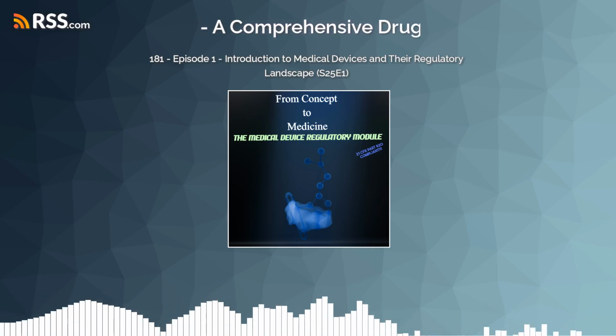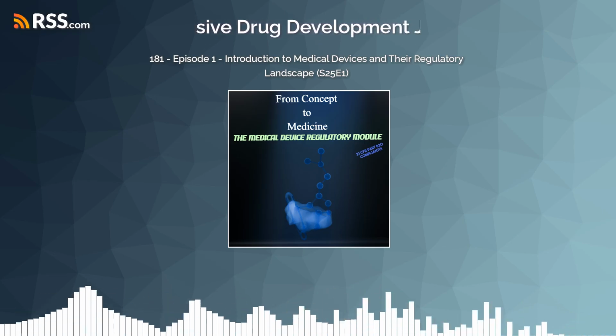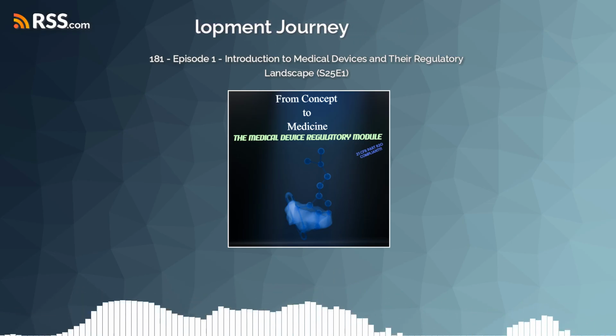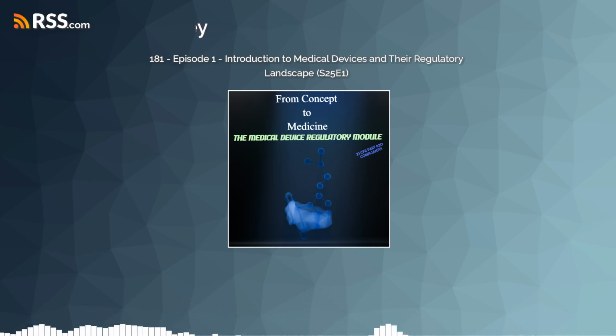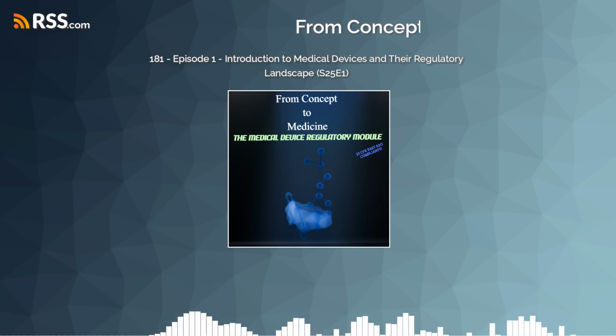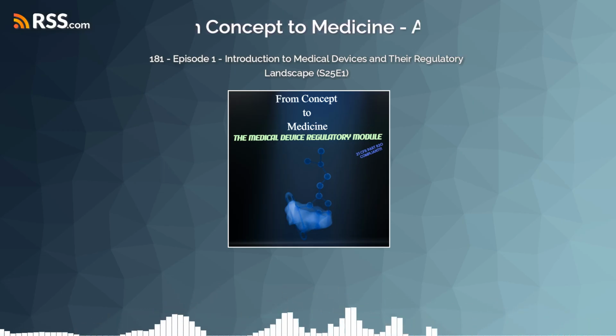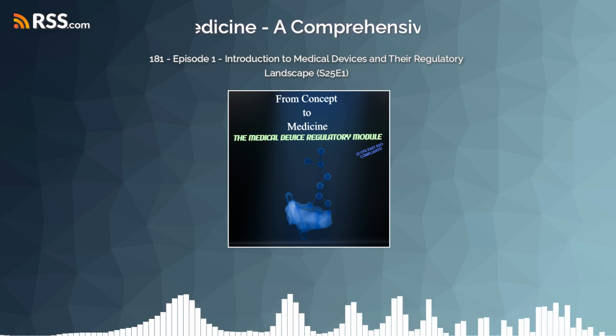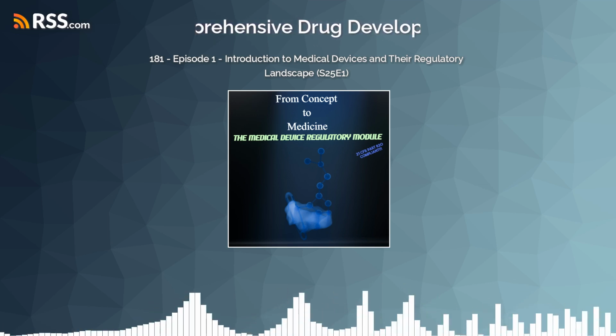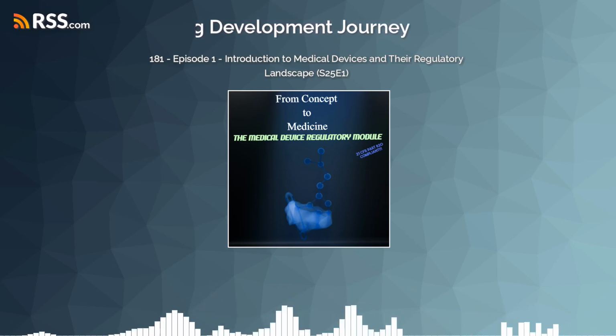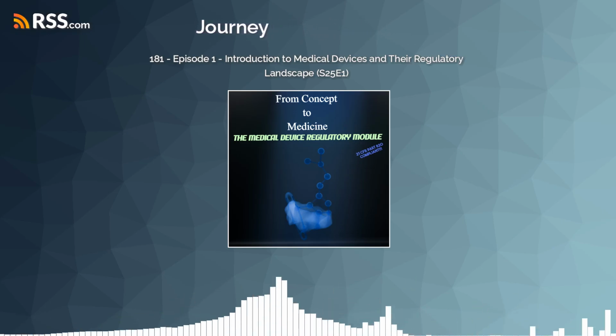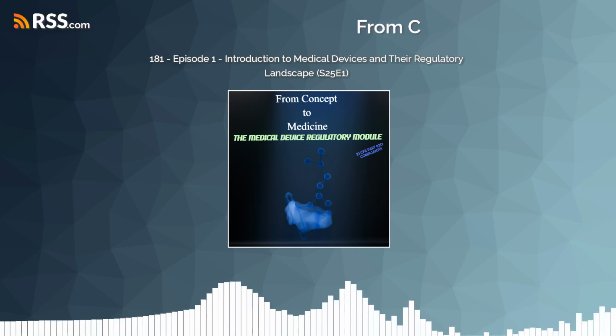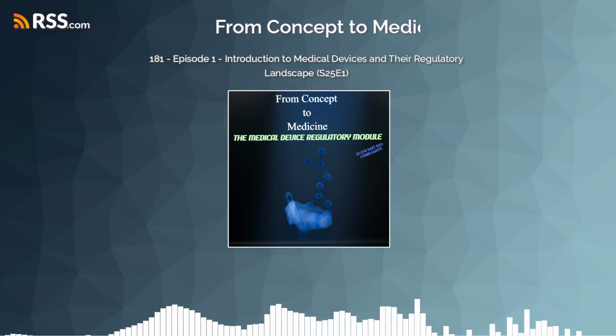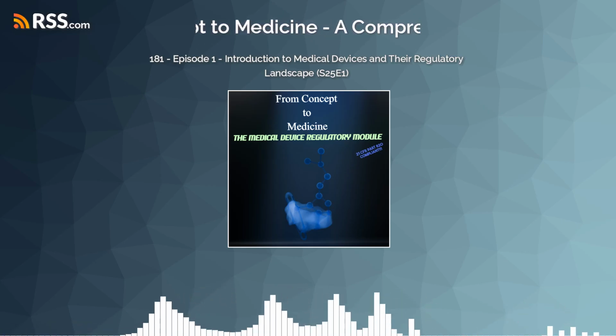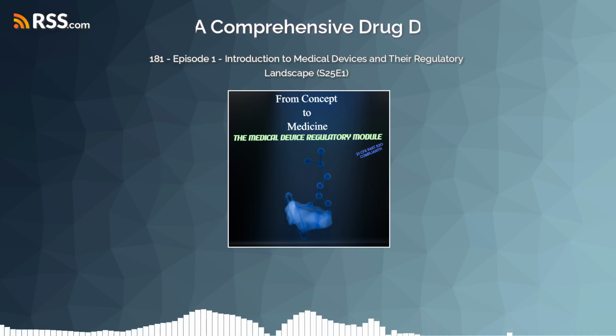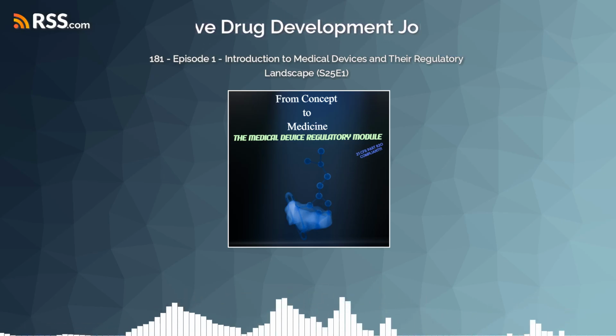But medical devices are a global business. Are there international efforts to maybe harmonize regulations? Or are manufacturers just facing entirely different rule books everywhere they want to sell? That's a great question. There are significant efforts towards harmonization, yes, but it's still a complex global tapestry. International bodies like the International Medical Device Regulators Forum, or IMDRF, work on developing converged regulatory practices. But different regions still have their own specific requirements. A major one, for example, is the European Union's medical device regulation, the EU MDR, regulation 2017/745. It replaced older directives and now governs device approvals across the EU.